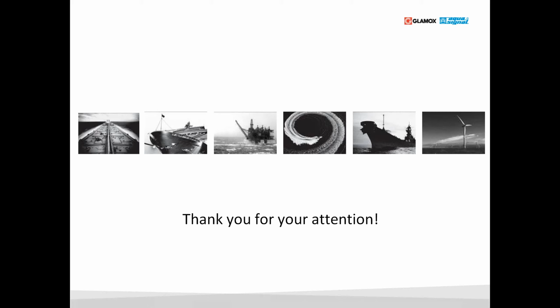Yeah, that has to do with the light settings, and as I said, 800 lumen is what replaces 18 watt fluorescent. So that has been the main runner. If you look at the fluorescent compact tubes, it has been only 18 watt. 1 times 18 watt, that's what you find everywhere.